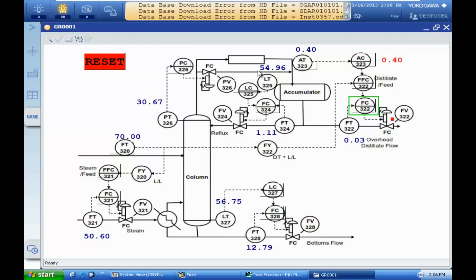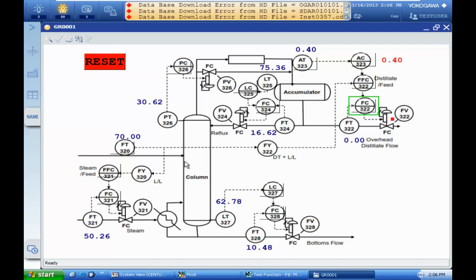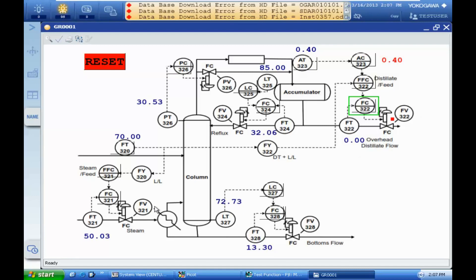We have more than 50 here, the reflux is increasing, and the level of the column will be increased. You can see that it's a very dangerous situation because we don't have any product output, steam is lined up to the system, and we just have a circulation — it's very dangerous.